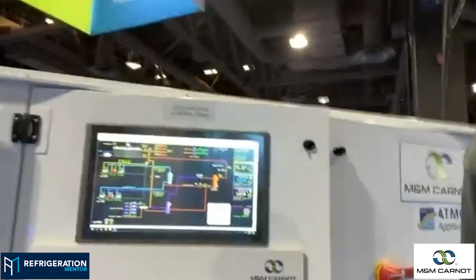And I was at a site last week and I just watched the manufacturer go in, and the contractor installed and did all the setup. And I go in and he's like, Trevor, I want to show you a few things. He goes into the control, you see all these electronic valves, they are just all on the default program, so nothing's been changed to really fine tune it. So that valve is working perfectly on temperature or superheat. And he's like, Trevor, you need to understand that this valve here affects other parts of the system.